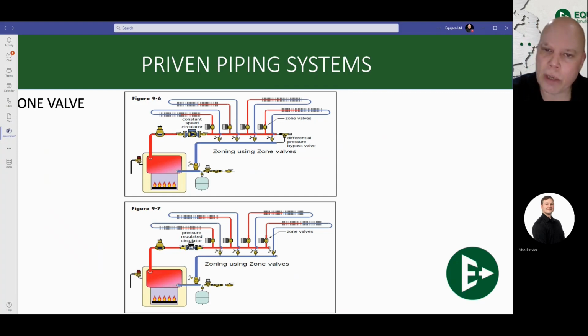Nobody wants that. So a differential pressure bypass valve is something that's going to be required when using a fixed speed circ. However, nobody uses fixed speed circs anymore. This is 2023 now, and the world has adapted, and we all use variable speed pumps now for pretty much everything. What these things do is modulate the speed of the pump up and down based on a couple of things, either pressure or temperature or a couple of other things. But in this case, we're going to put in a pressure regulated variable speed circulator.